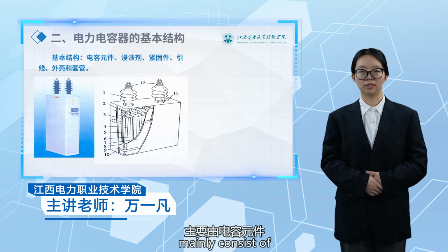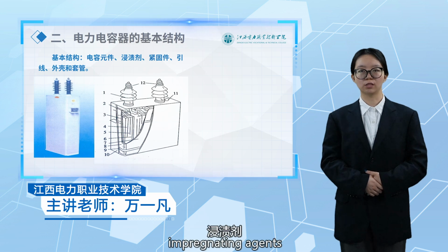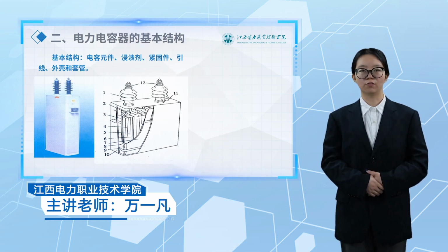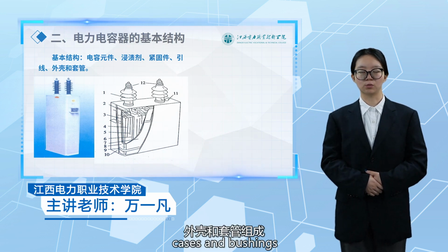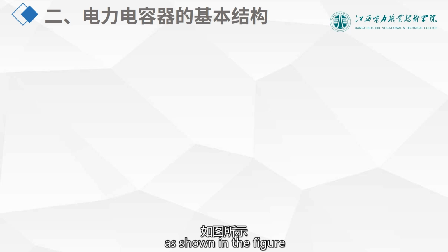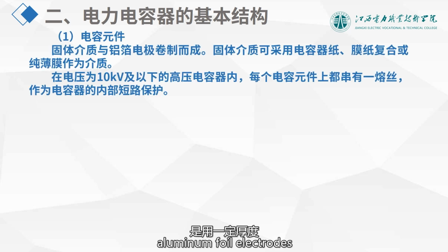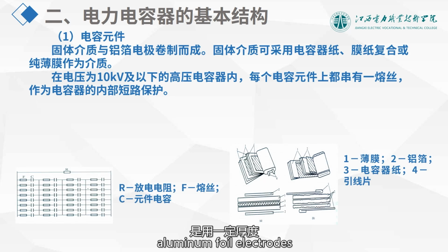Shunt capacitors mainly consist of capacitor elements, impregnating agents, fasteners, leads, cases, and bushings, as shown in the figure. Capacitor elements are made by winding aluminum foil electrodes with a certain thickness and layers of solid dielectric, as shown in the right figure. In high voltage capacitors with voltage of 10 kV and below, each capacitor element has a fuse in series for internal short circuit protection.